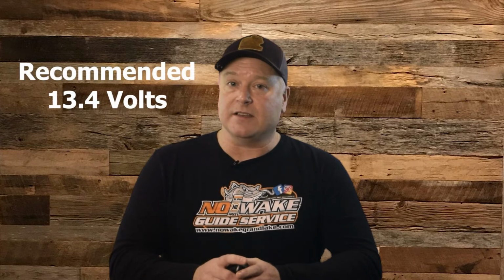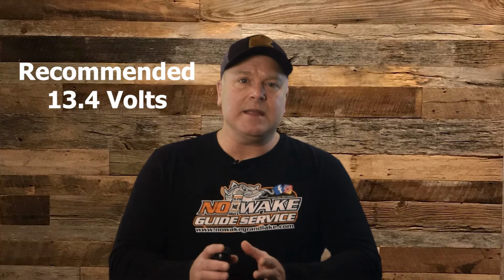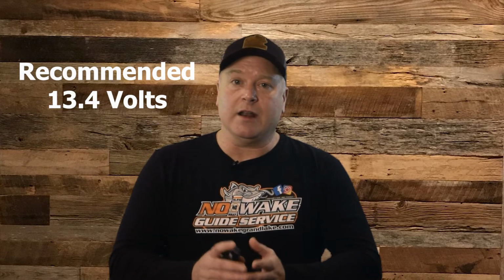If you start the night with low batteries and expect the converters to carry the load while the batteries charge, they will generate 14.6 volts. And for 2 converters, you could be pumping more than 29 volts to your 24 volt devices. A good bet is to get a converter that can put out a constant voltage and set it slightly in excess of 13 volts. And try to keep the batteries charged, both on and off the water.